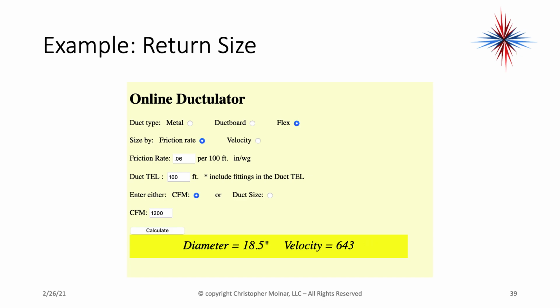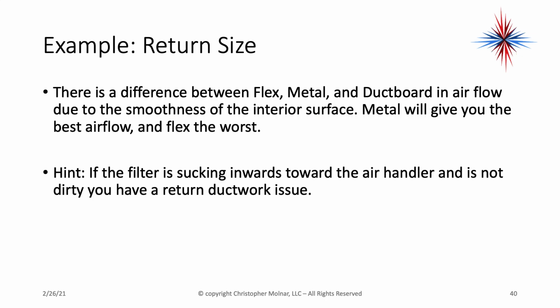Okay. So my return ductwork at a minimum should be 18.5 inches diameter. There's a difference between flex, metal, and ductboard in airflow due to the smoothness of the interior surfaces. Metal will give you the best airflow, flex the worst. A hint: if the filter is sucking inwards, in other words, you see an air filter that is bowed inwards towards the air handler, and it is not dirty, you have a return ductwork issue. The ductwork's too small. It's trying to pull too much air through that filter.